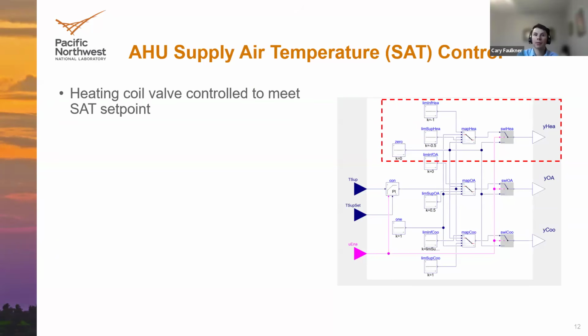I mentioned the central air handling unit has both a heating coil and a cooling coil, which have water sources and valves to control the water flow through those coils. So that first aspect is going to take information from this PI block based on the measured supply temperature and the set point for the supply temperature, and it's going to be fed up into this block here and determine, based on those measurements and some mapping, how much heating is needed at the central air handling unit to meet the set point.